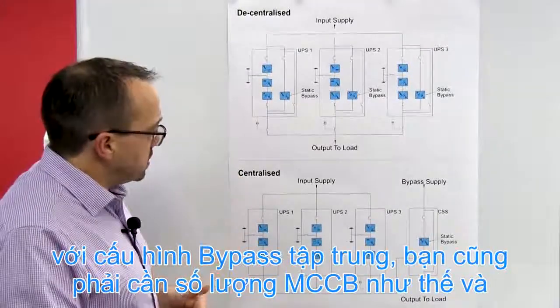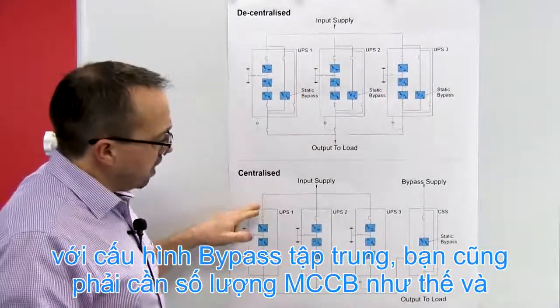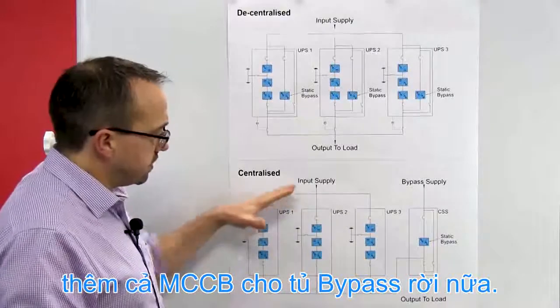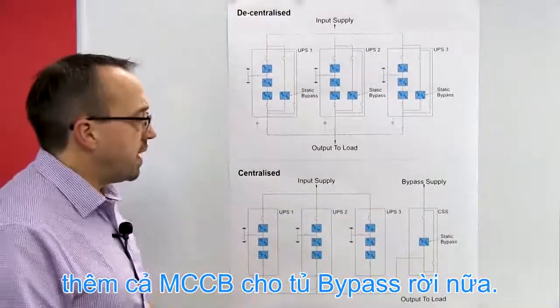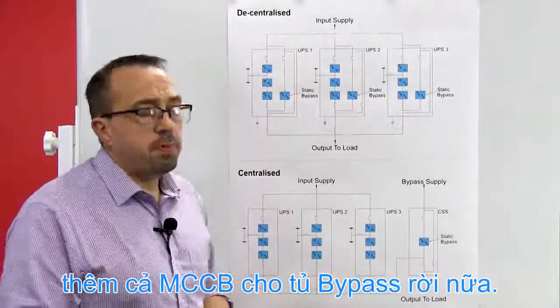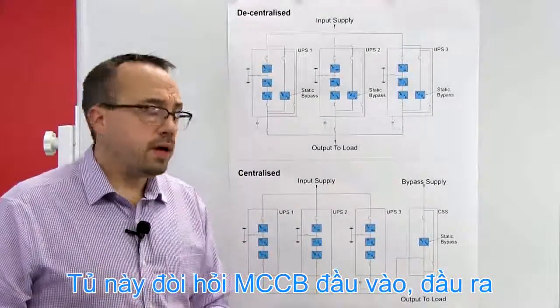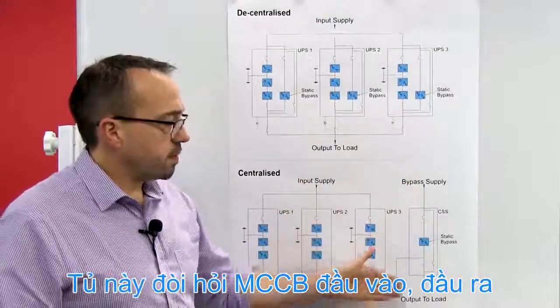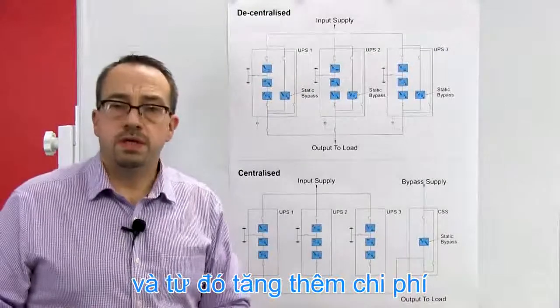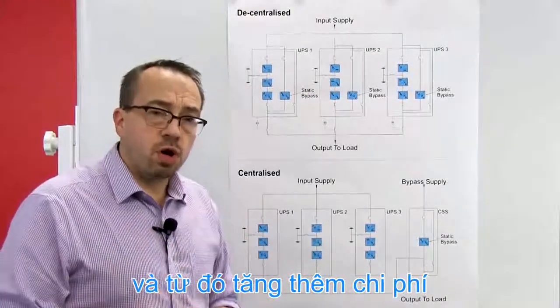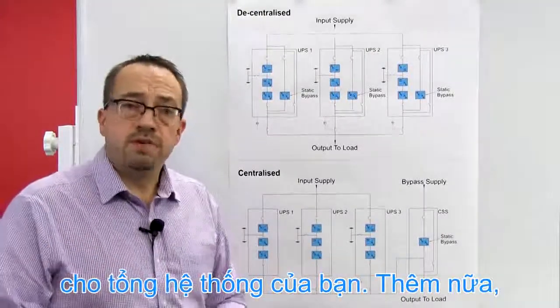However, with the centralized system, you still have the same number of input breakers and output switches for the UPS modules. However, now you have a separate bypass cabinet which would also require an additional supply circuit breaker and an additional output load switch, and therefore that can increase the cost of the electrical switchgear around the system.